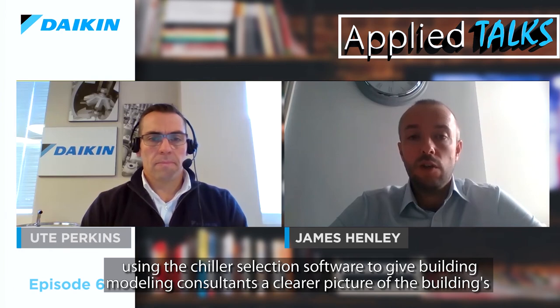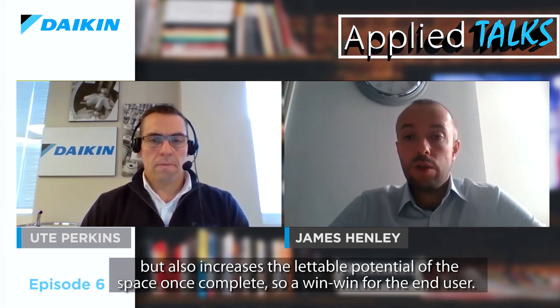Yeah, well, firstly, the units are all eco-design tier 2 compliant, so there's no issue for upcoming legislation changes and the efficiency targets required. But also in the UK, the high efficiency can be calculated for site-specific conditions using the chiller selection software to give building modelling consultants a clearer picture of the building's energy use prior to installation and achieve higher energy efficiency rating for the building overall. This higher rating also reduces energy use, but also increases the lettable potential of the space once complete. So it's a real win-win for the end user.